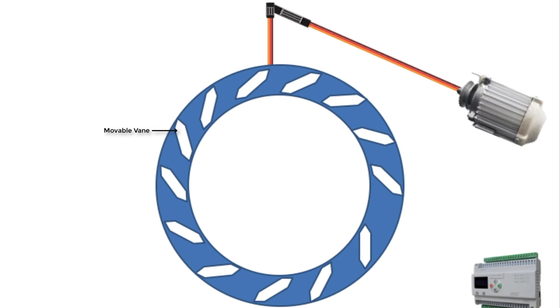The vanes position or the angle is adjusted by the control ring connected to the electric positional motor via a reduction gear. The control system governs the action of the microprocessor controlled positional motor.